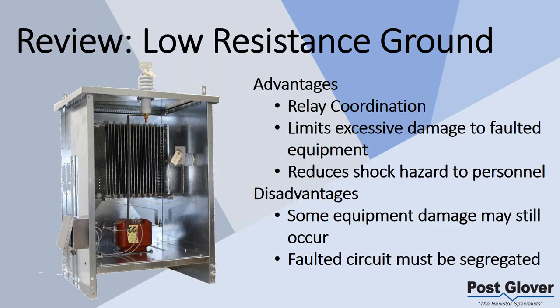Your resistance and current are inversely proportional. So the higher you go up with resistance, the lower your current's going to be, and vice versa. So the advantages of a low resistance ground system are relay coordination and reduced damage to equipment.